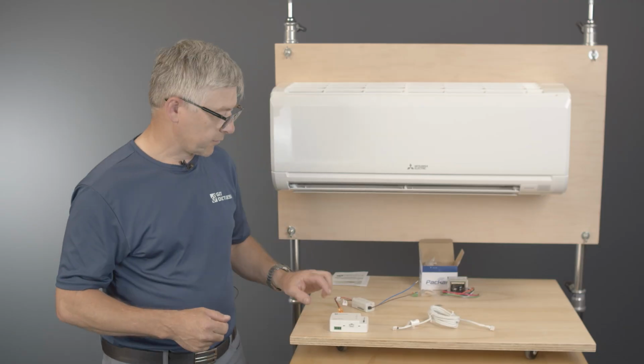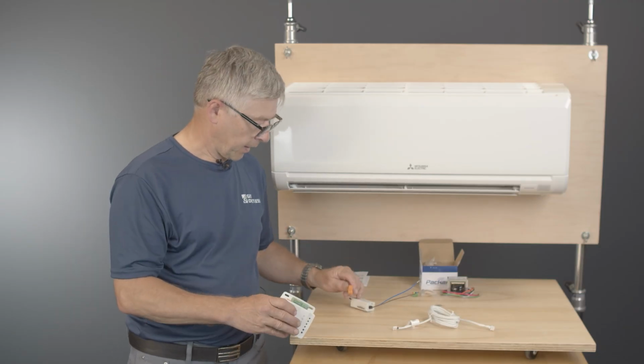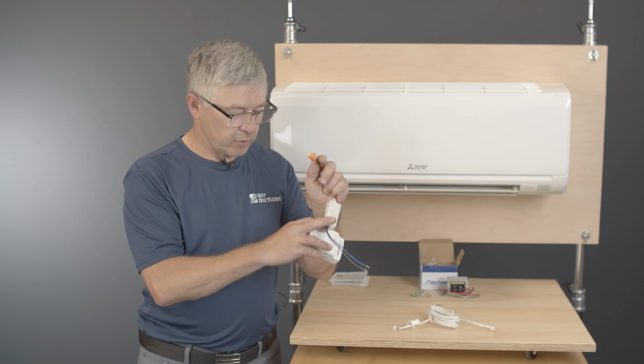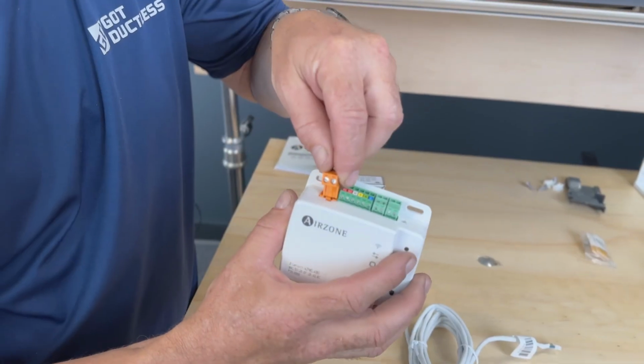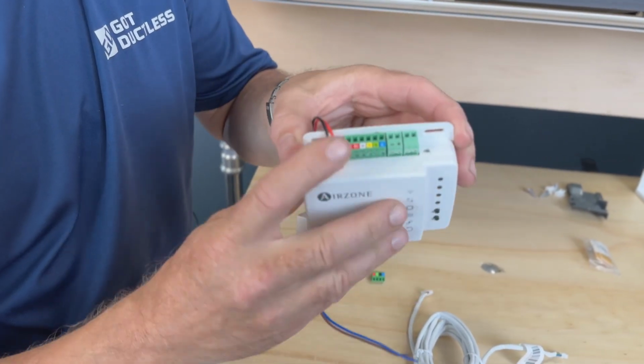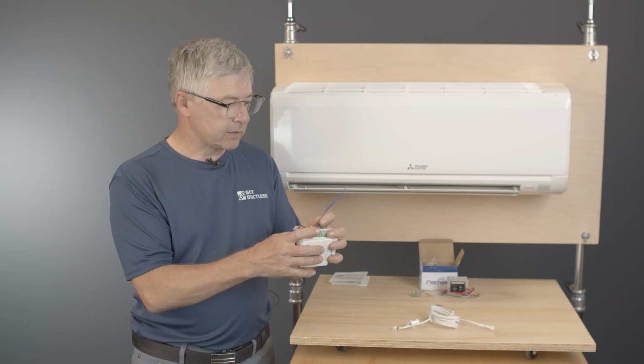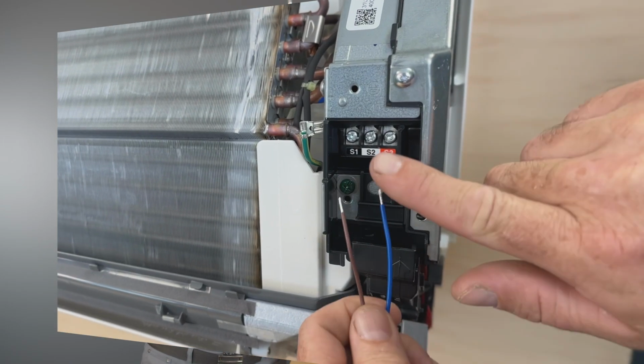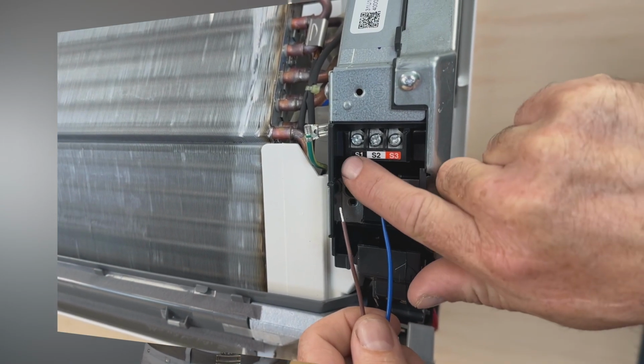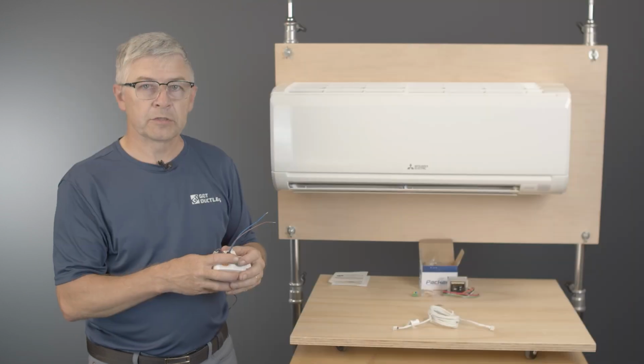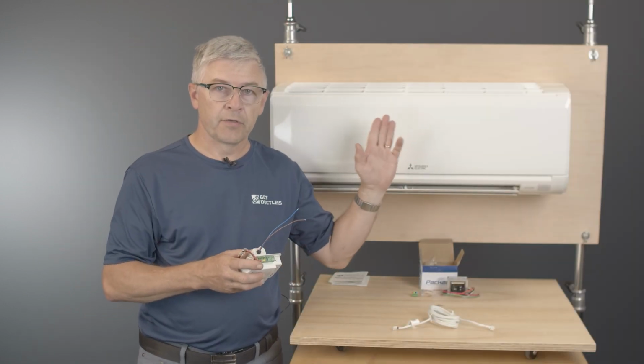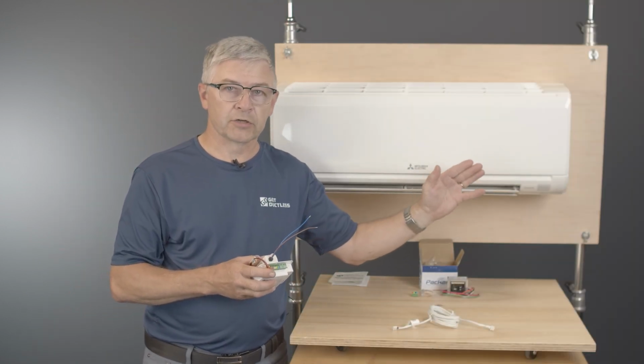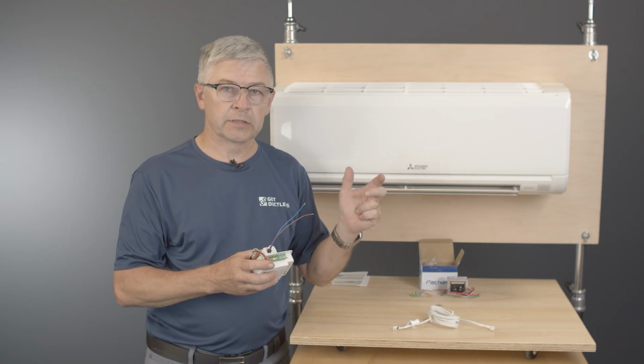Let's take a closer look at the wiring. The internal transformer connects right here, orange to orange—really hard to miss—and the other end connects to the S1, S2 high voltage terminals on the air handler. All Mitsubishi air handlers will have 3 power and control terminals: S1, S2, S3.